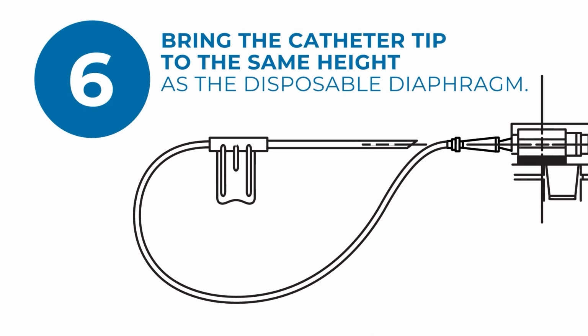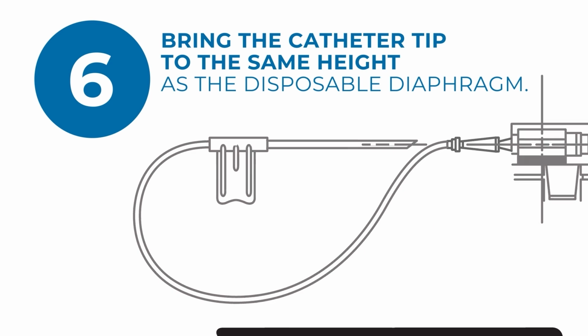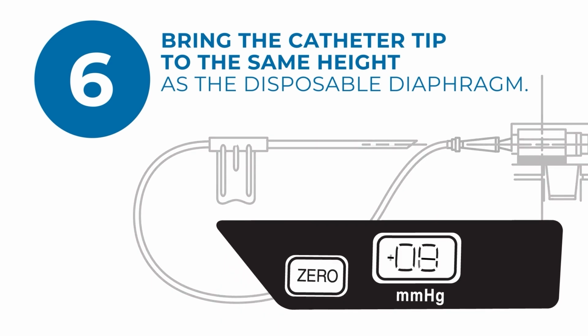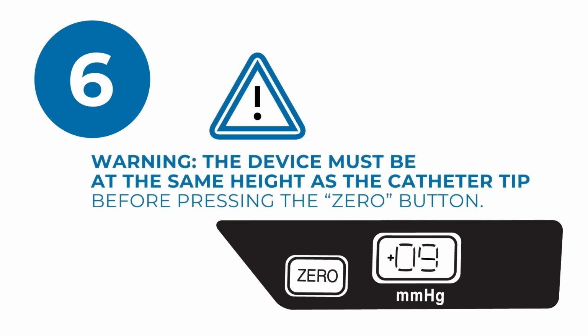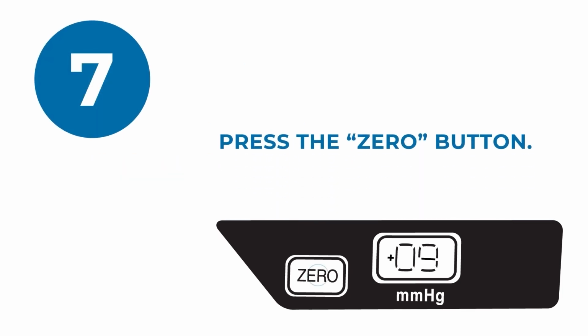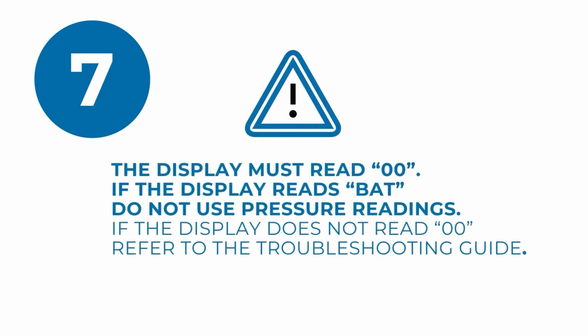Next, bring the catheter tip, the slit end, to the same height as the disposable diaphragm. The display should read between -8 to +9 millimeters mercury. To ensure accuracy, the device must be at the same height as the catheter tip before pressing the 0 button. When the display is in the correct range, press the 0 button and wait 2 seconds until the display reads 00. The display must read 00. If the display reads BAT, you must replace the battery and repeat steps 6 and 7 to obtain an accurate pressure reading.